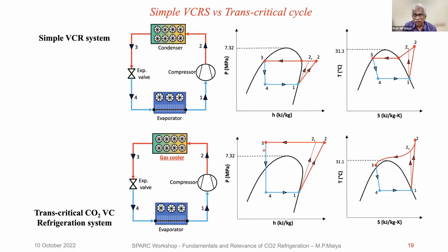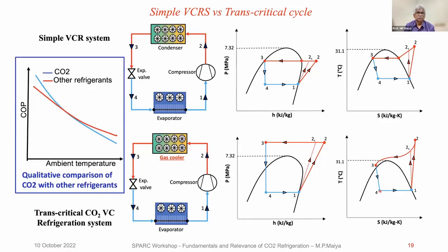Then 3-4: you can see here that 3 is above the critical line, which means it is gaseous. As you throttle it, as it flows through the capillary tube or whatever it is, it becomes 100% liquid and then enters the two-phase region. So it goes transcritical, from supercritical to subcritical, from 3 to 4. That is the difference. Because of this high-pressure gas being throttled, a lot of energy, exergy, is lost.